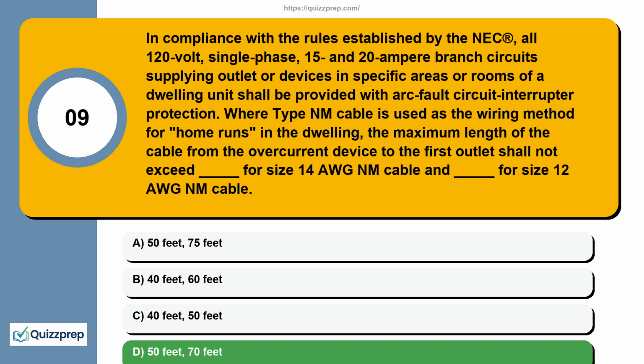Section 210.12 of Article 210, Branch Circuits, explains the rules for AFCI protection. 210.12(A)(4)(b) calls for the conductors to have length restrictions to the first outlet from the overcurrent device, based on the size of the conductors, 50 feet for 14 AWG and 70 feet for 12 AWG conductors.